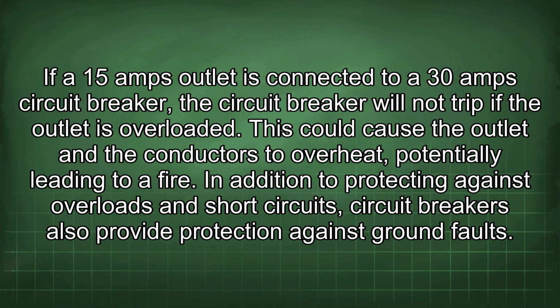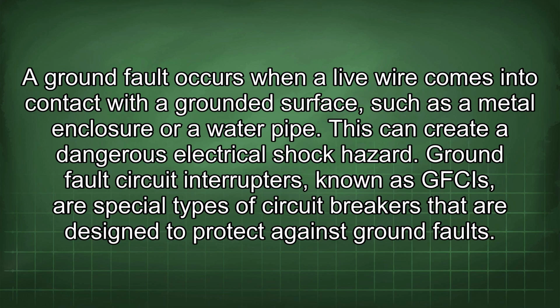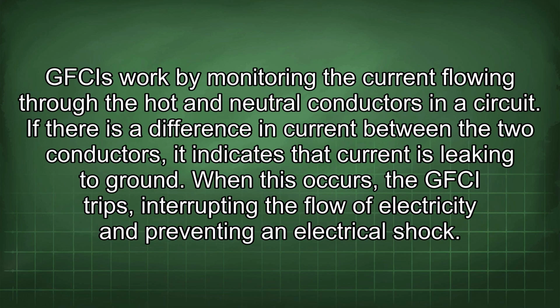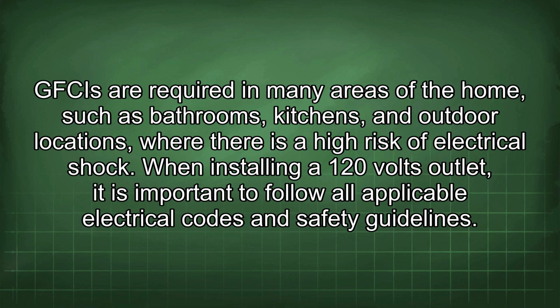In addition to protecting against overloads and short circuits, circuit breakers also provide protection against ground faults. A ground fault occurs when a live wire comes into contact with a grounded surface, such as a metal enclosure or a water pipe. This can create a dangerous electrical shock hazard. Ground fault circuit interrupters, known as GFCIs, are special types of circuit breakers that are designed to protect against ground faults. GFCIs work by monitoring the current flowing through the hot and neutral conductors in a circuit. If there is a difference in current between the two conductors, it indicates that current is leaking to ground. When this occurs, the GFCI trips, interrupting the flow of electricity and preventing an electrical shock. GFCIs are required in many areas of the home, such as bathrooms, kitchens, and outdoor locations, where there is a high risk of electrical shock.